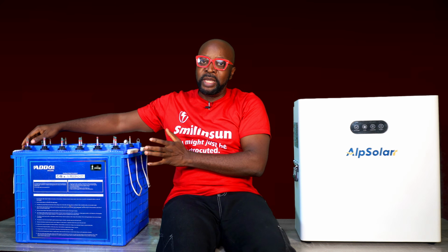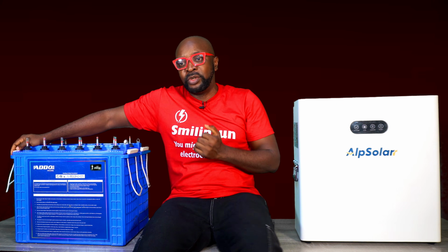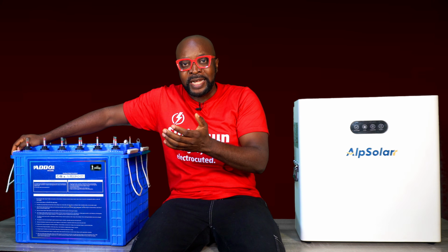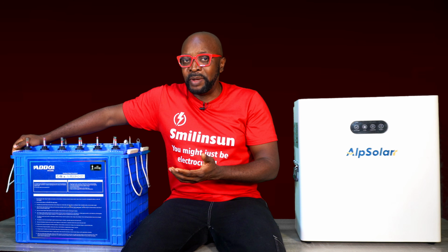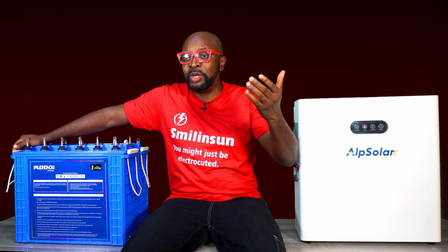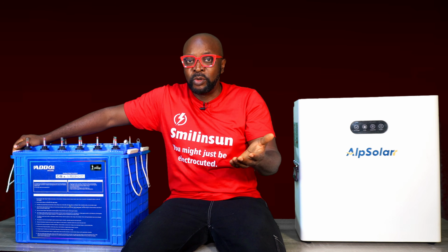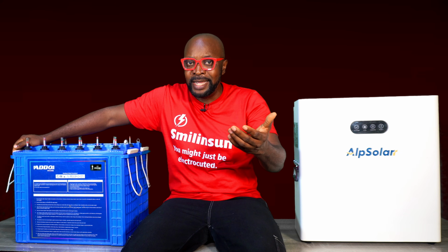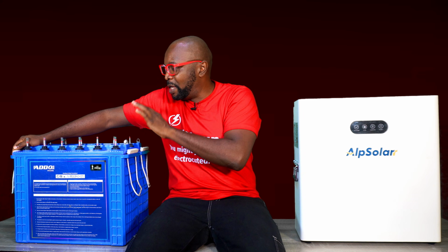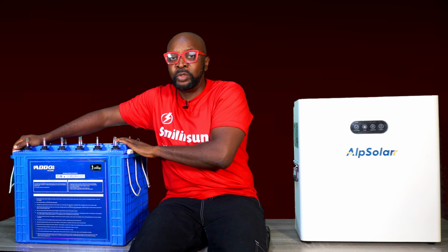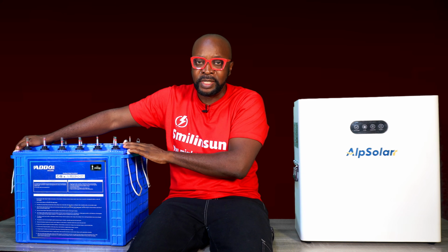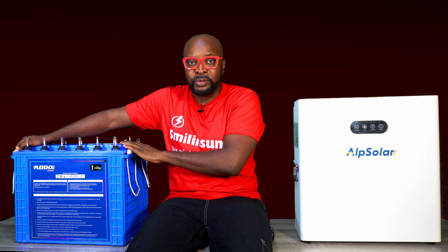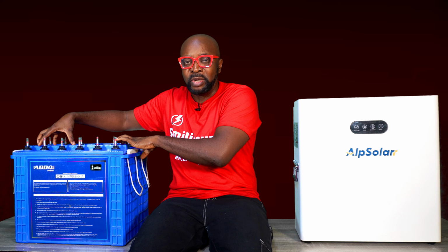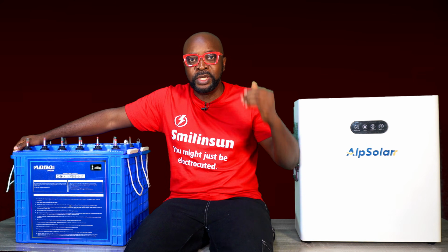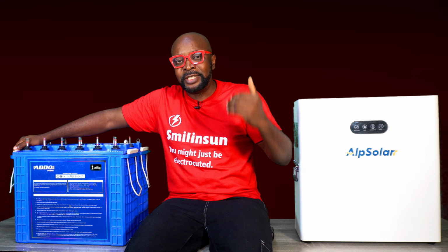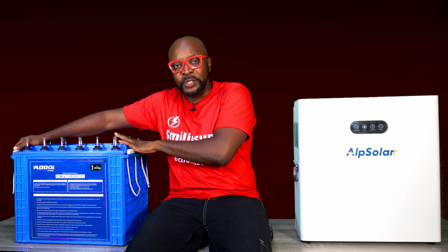But the tubular battery doesn't have any communication cable that you can use to connect the battery to the inverter. So the battery will have to depend on the parameters that you've set on the inverter to be able to charge. The inverter is going to rely on you to give it all the accurate information it needs to charge this battery. So you will have to extract all the right parameters, the charge voltage, the low cutoff voltage, the charge current, everything that this battery needs, and manually input it on the inverter for that charging system to be smooth and healthy for this battery.